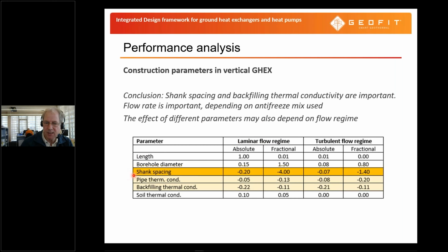And here you can see that especially shank spacing has a big effect. And second are pipe thermal conductivity and backfilling thermal conductivity that also add to the effect on the thermal resistance of the borehole. So shank spacing is actually an important parameter to consider, especially in the laminar flow regime. In a turbulent flow regime, it becomes a smaller effect on the overall thermal resistance.